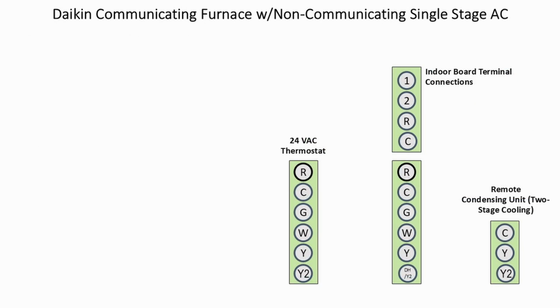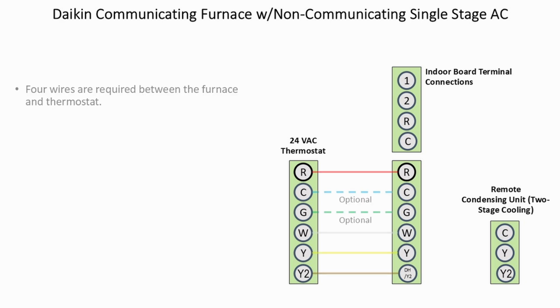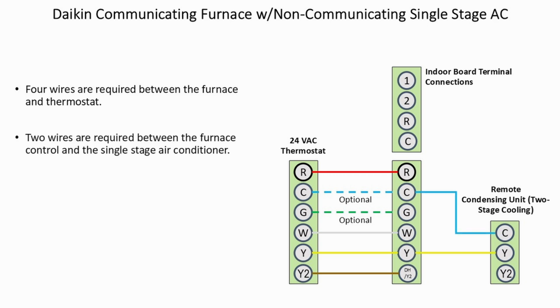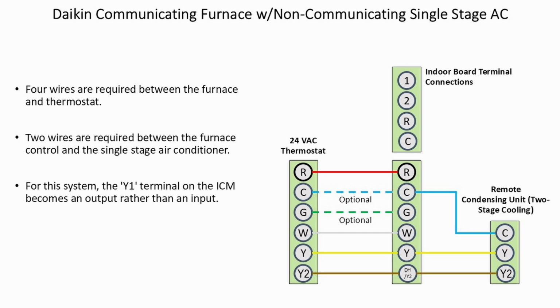Daikin communicating furnace with a non-communicating single-stage air conditioner. 4 wires are required between the furnace and the thermostat. 2 wires are required between the furnace control and the single-stage air conditioner. For this system, the Y1 terminal on the integrated control module becomes an output rather than an input.